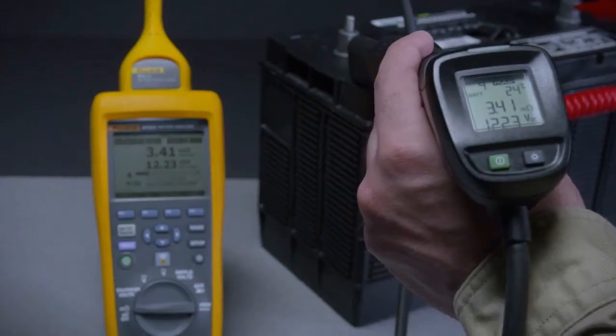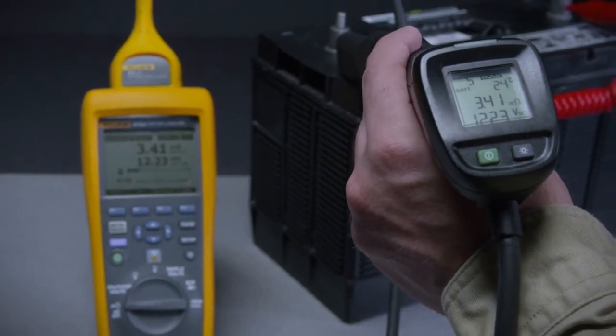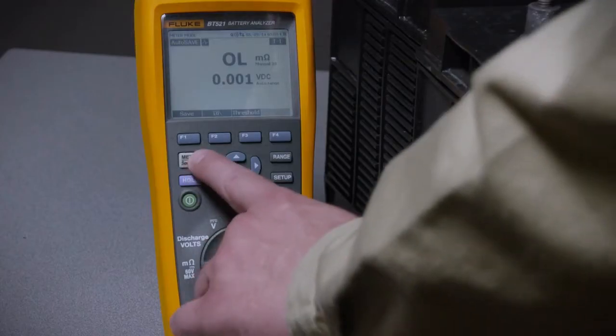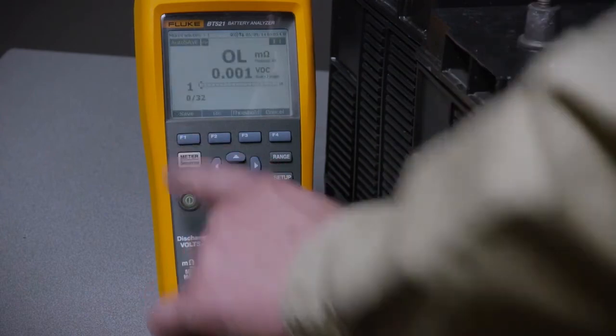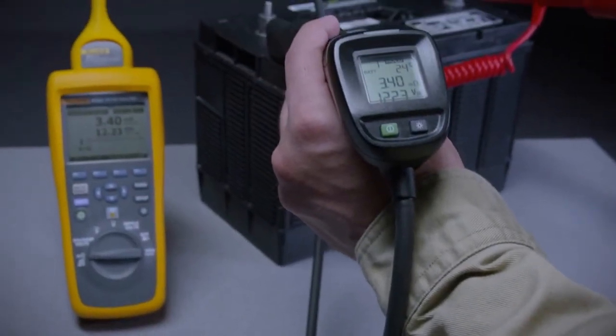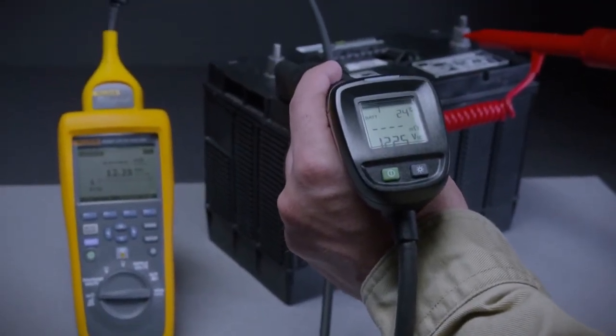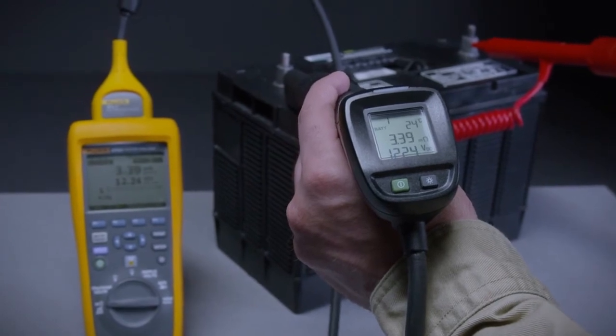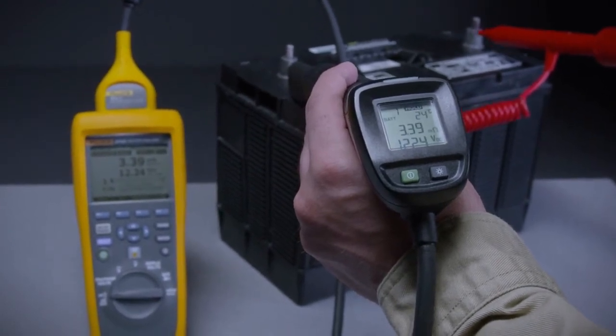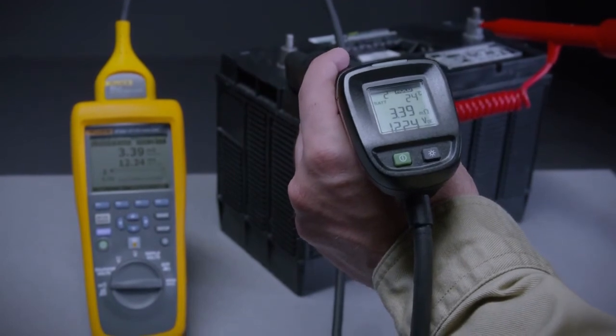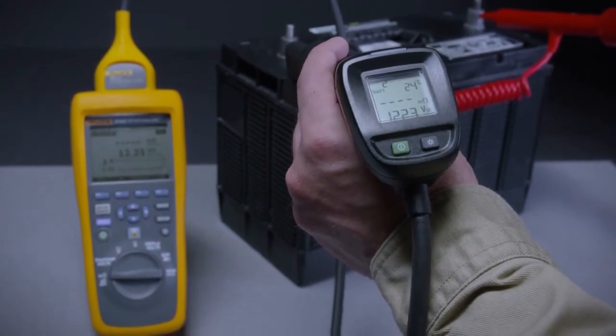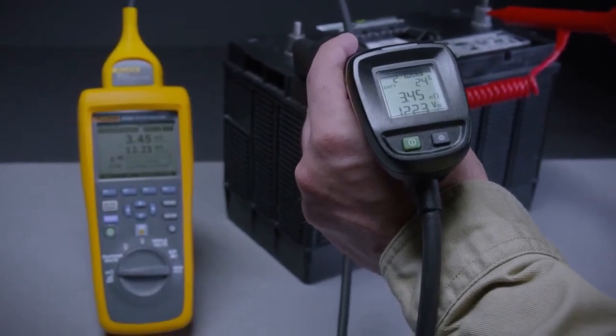We can also use the intelligent probe in the sequence mode. Simply enter into sequence mode on the instrument, then begin taking the required measurements, specifically voltage and battery resistance. The display on the probe handle indicates that the reading has been taken and saved, and the probe uses verbal cues to indicate which measurement in the sequence has been made.